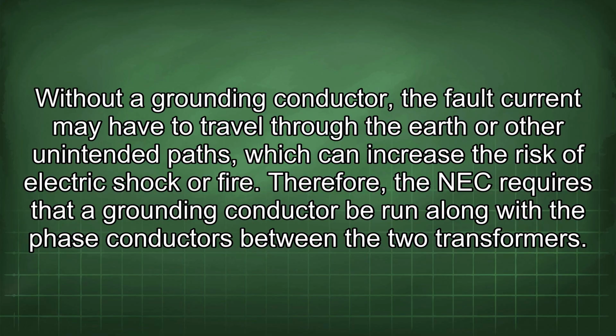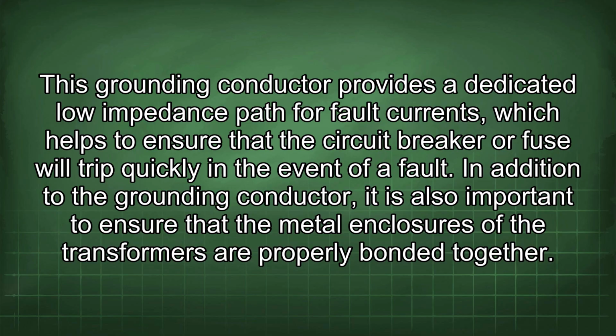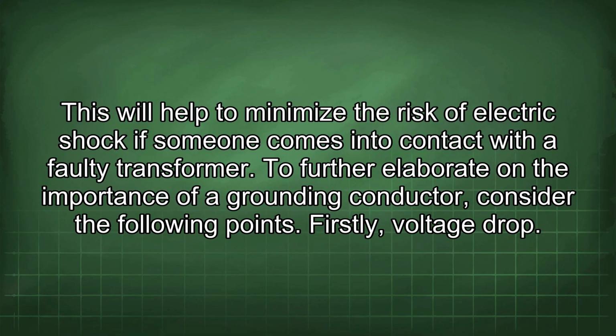Therefore, the NEC requires that a grounding conductor be run along with the phase conductors between the two transformers. This grounding conductor provides a dedicated low impedance path for fault currents, which helps to ensure that the circuit breaker or fuse will trip quickly in the event of a fault. In addition to the grounding conductor, it is also important to ensure that the metal enclosures of the transformers are properly bonded together.